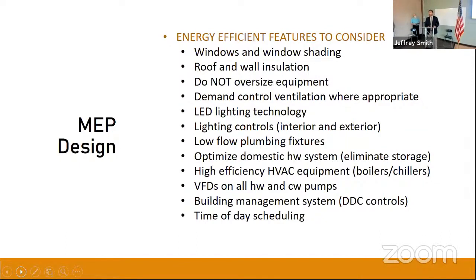Ventilation air from the outside, you have to heat and cool it. That is a large portion of your energy usage. If we can employ different technologies such as carbon dioxide sensors in large rooms such as this, that monitor the level and adjust the outside air to a level that's needed rather than a fixed open position, that will help you save energy down the line. So we're looking at those technologies as well.